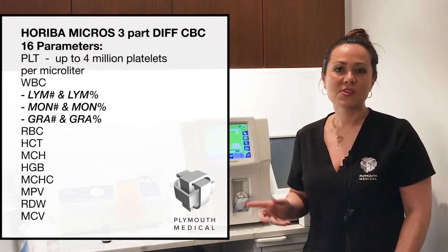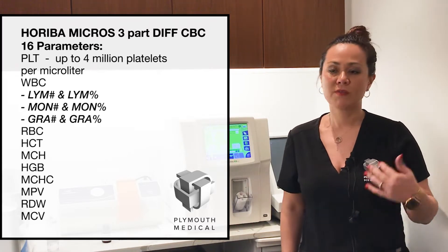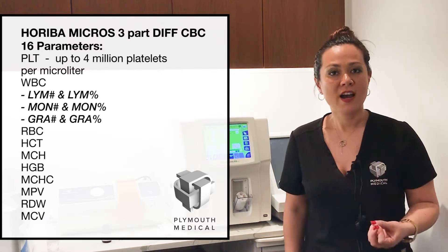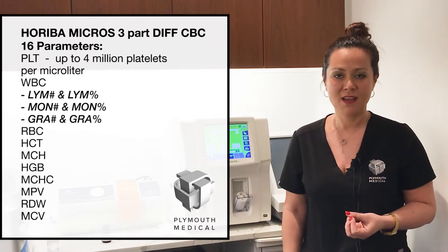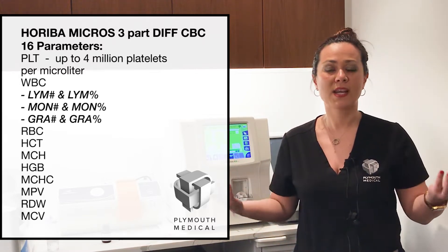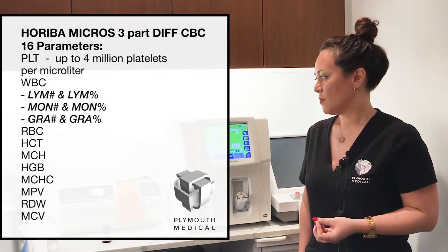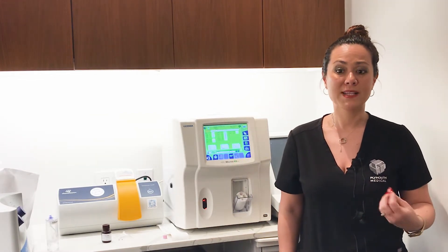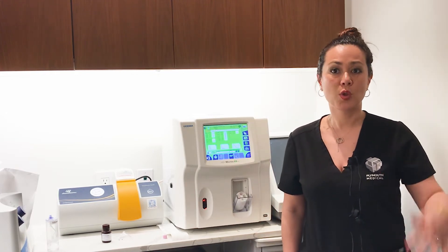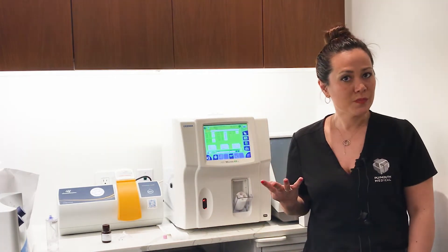That's quite key because this device is actually cleared by the FDA for up to 4 million platelets per microliter, which for those of you that know anything about hematology is quite key. When you're using a high-yielding PRP system such as our EmCyte PurePRP, you're often able to concentrate platelet concentrations up to 20 times baseline. Most hematology analyzers will cap your platelet range at around the 2 million mark, with this being twice that amount at 4 million platelets per microliter.